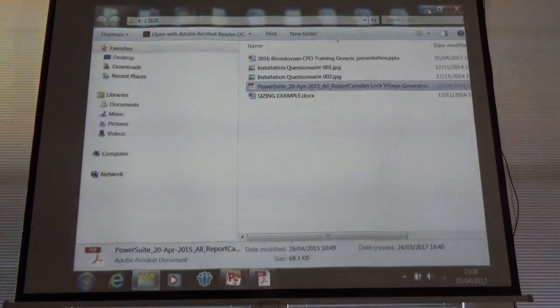So the sub caveat of prime, LTP, basically says the ISO standard says you can run 100% of its rating for up to 500 hours per year. And guess what? The Cummins product actually goes over and above the standard. It says you can run up to 750 hours per year. So again, the knowledge of the different manufacturers and their limitations allows me to make the recommendation of the best engine alternator combination to fit your requirements.